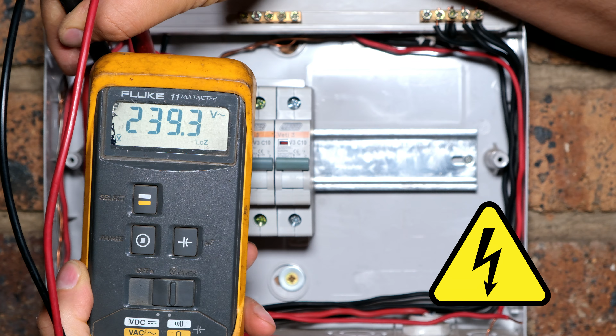Now what I want to show you is that I have put my meter on that circuit breaker, and notice that there is still a voltage there, 239 volts. So even though this is down, there is still a shock hazard on this part of the distribution board. Please be very careful. If possible, try to switch off any in-feed to this board. If you cannot, just be careful when working around this part.